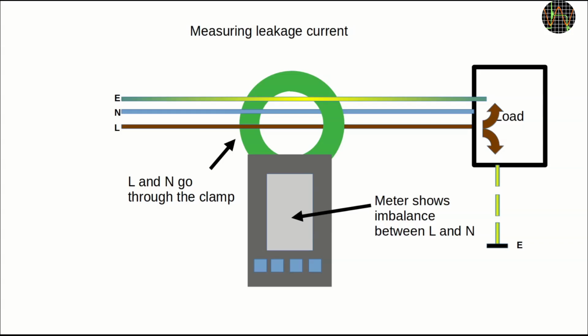Leakage occurs, for example, when for some reason not all the current in the L wire is flowing back to the N wire. There could be some current flowing to the E wire, or there could be another path to earth that takes some part of the current. Most importantly, that path could be you, sticking a knife into a toaster to get some bread out. To save you from harm, most modern house installations have a thing known under many names like RCD, RCCB, RCBO or GFCI. This device compares the current on the L and N wires, and if it detects an imbalance, it breaks the circuit, thus saving you. They usually trigger within milliseconds when the imbalance exceeds 30 milliamps, and they usually have a test button causing a deliberate imbalance, allowing you to check that they still work.